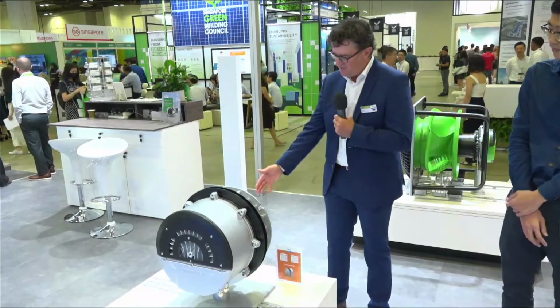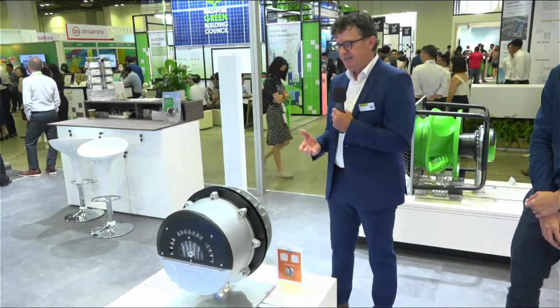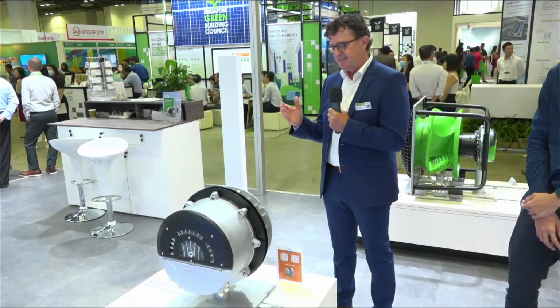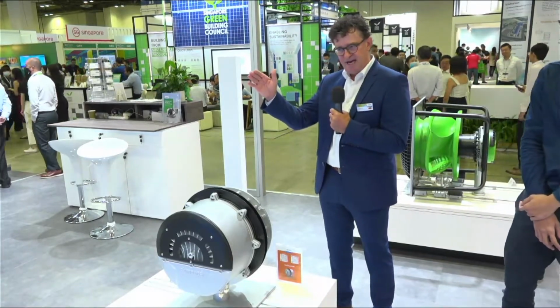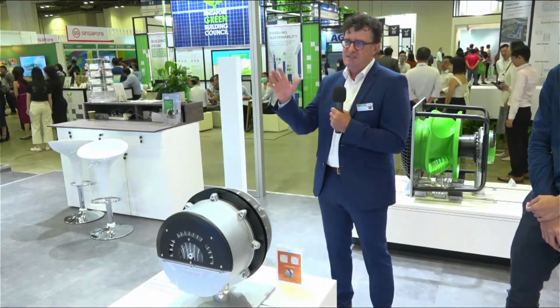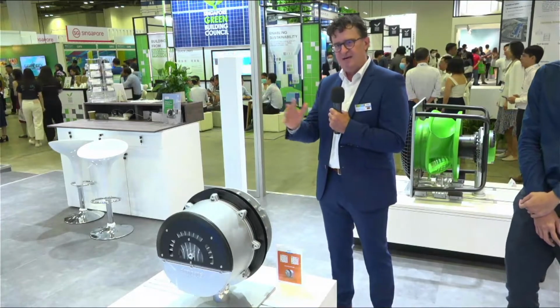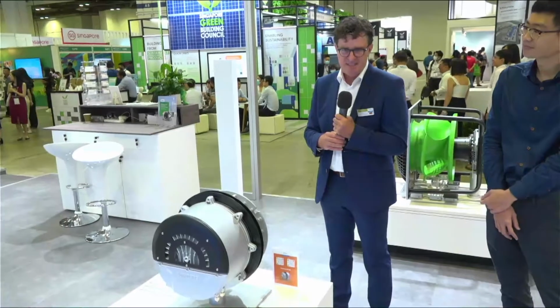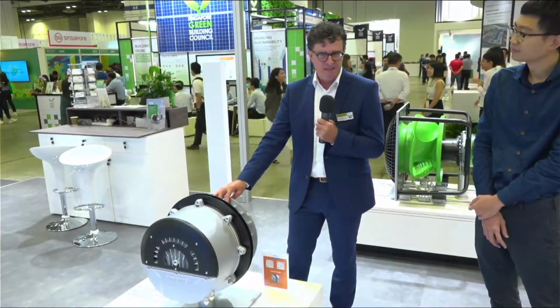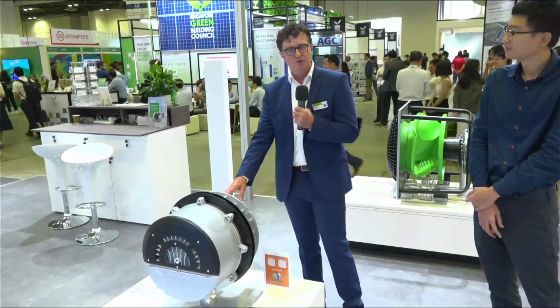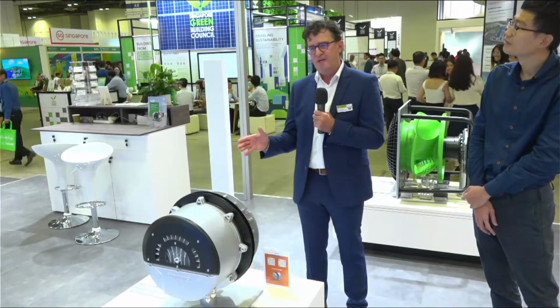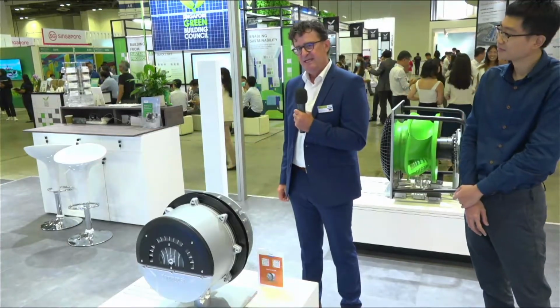But we offer this motor also as a motor only, and then we have an extended shaft on one side of the motor where our customers can put their axial impeller on it. The speed designed for the use with axial fans is 700 down to 400 RPM, and especially in this area, when it's modulated, the efficiency is kept at a very high level. The maximum efficiency of the motor is about 95%. And as mentioned, this is a unique product. It's a worldwide unique product, and there's no EC motor worldwide that offers these features. On top, this motor uses permanent magnets, but these permanent magnets do not use any rare earth material. So this is also our sustainable approach to EC technology.